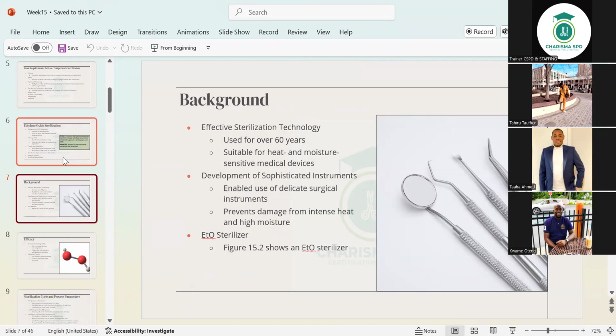So the background you just need to know is that ethylene oxide has been around for over 60 years, which means it's good to be around until this time. And then we've told you about heat sensitive items. Yeah. ETO sterilizer, I don't think we have a very good image of it here, but they are just like the normal sterilizers we see, but their mode of working is a bit different, because remember, they are using ethylene oxide instead of the steam that we looked at yesterday. But your job is going to be to use the parameters that are set down, put them in, and load it properly. As we said yesterday, the loading is going to be your work. Make sure you load it properly and carefully, and when you are offloading it too, properly and carefully, okay?